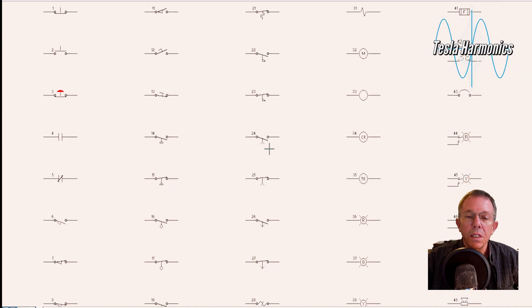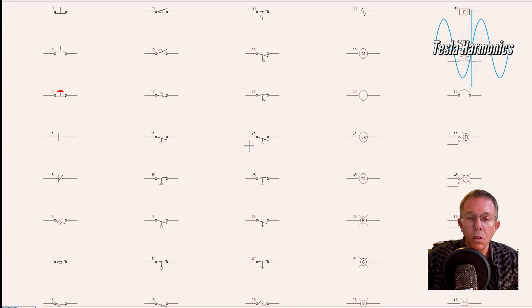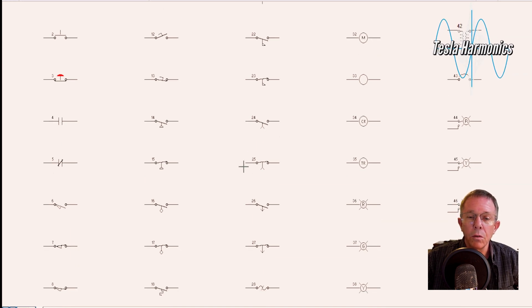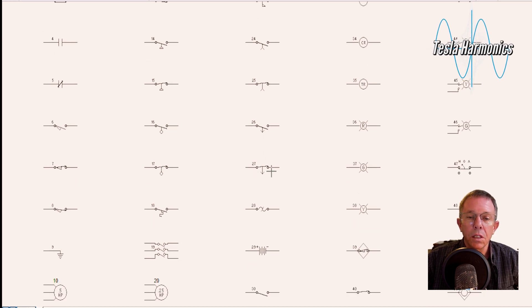Then we come to a time contact. When we look at contacts that have arrows on them, that means it's going to be a time contact, and the contact is going to time in the direction that the arrow is pointing. This normally open contact with the arrow pointing up is going to time to close — a normally open, timed close contact. The next one is closed and going to time to open — a normally closed, timed open contact. Then we have a normally open, timed open contact, and a normally closed, timed close contact.